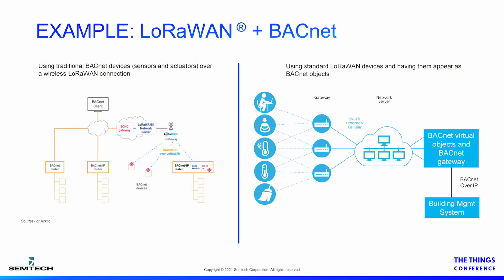The primary protocol used in building automation is BACnet, although there are many other options available on the market. However, BACnet generally is assumed to run over a wired connection of some type, so adding wireless options dramatically expands the use possibilities. Shown here are two examples of how LoRaWAN can be used in a BACnet environment.